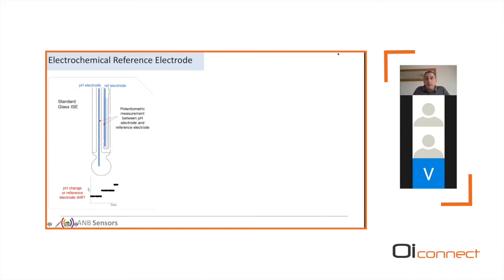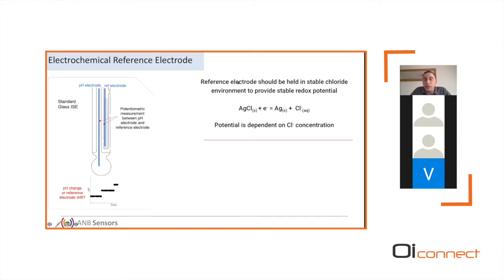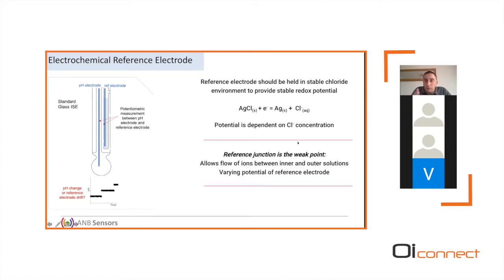So where do we sit with our technology? Our main technology is around reference electrode drift and understanding that and monitoring that. If we look at a conventional glass pH electrode, and this technology works exactly the same for the ISFET, we have a pH sensor which has to be referenced to a reference electrode. That reference electrode is normally housed within a chamber through a sort of a membrane. Over time, ions leach from that chamber and cause drift in our reference electrode. This is dominated by the chemistry, the silver-silver chloride chemistry of the reference electrode, and you can see the redox potential will vary depending on the chloride concentration, which isn't good when you're in deployment where the chloride concentration varies.